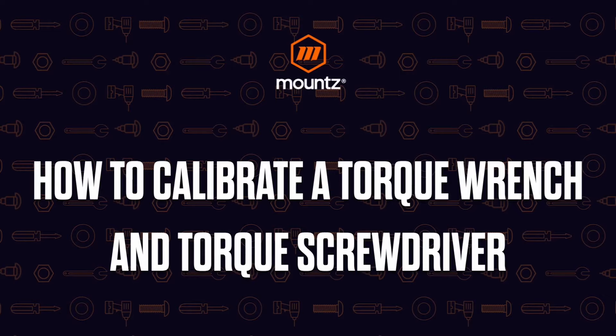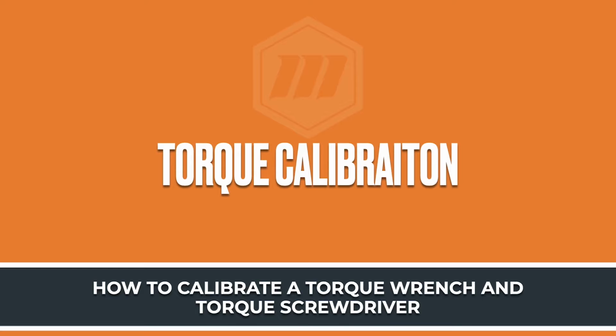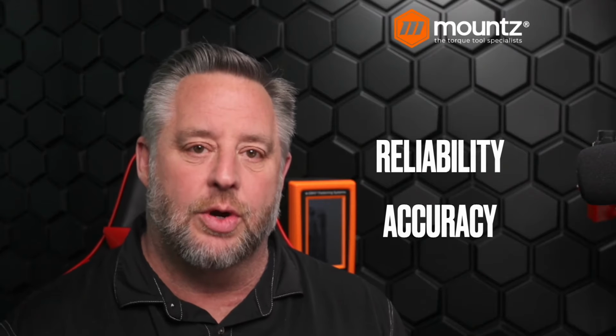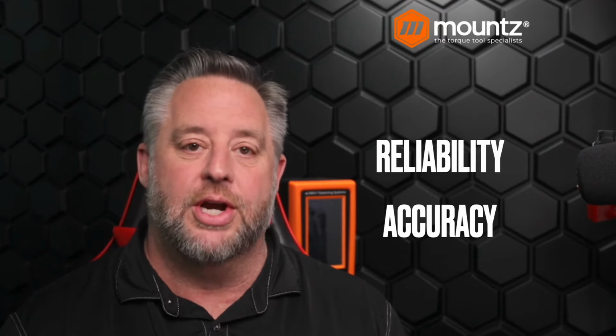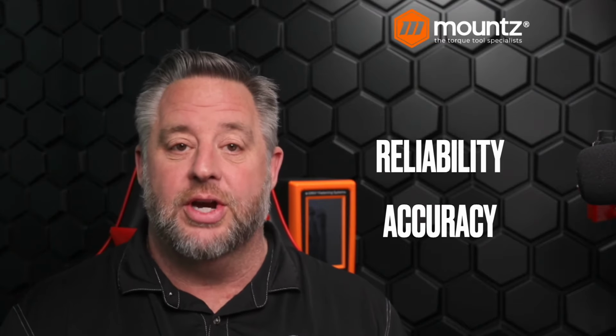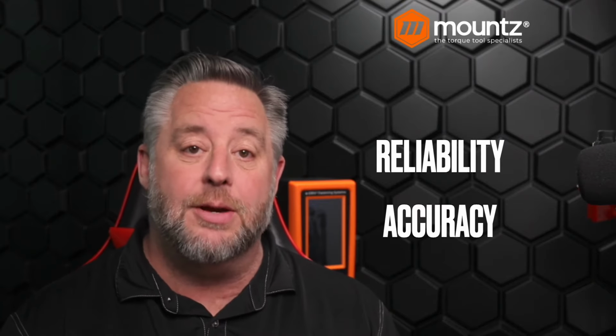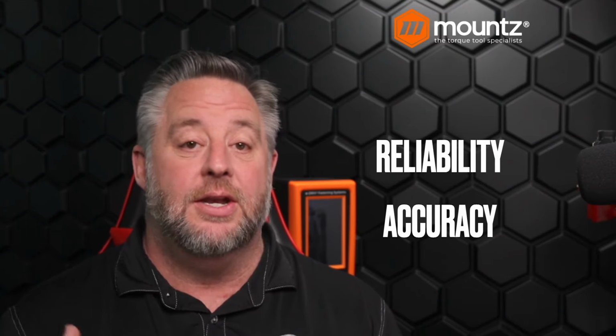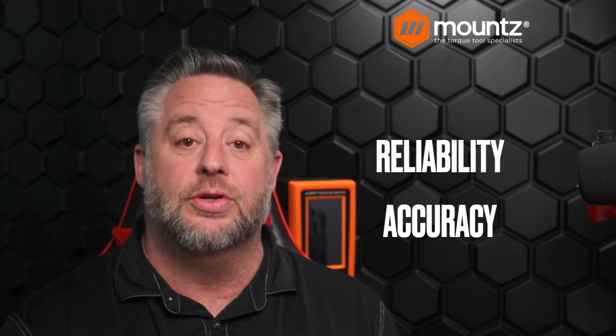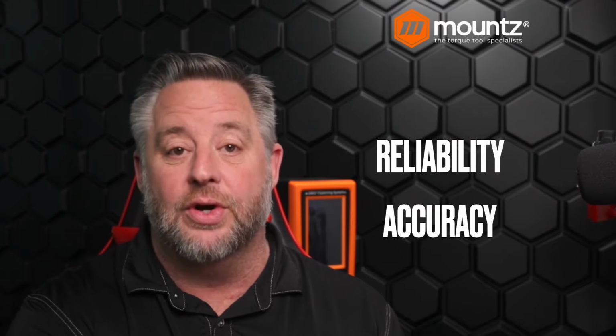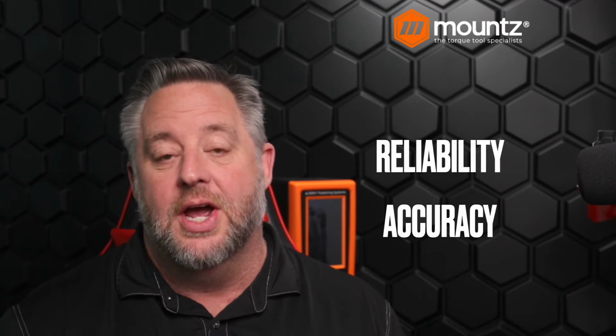But our topic for today is how to calibrate a torque wrench or a torque screwdriver. Now, the process of doing a torque calibration is not very difficult to understand or do, but there are some things that require a little bit of knowledge to know what's going on and how different things may affect the actual calibration process. The reason that we do torque calibration is to make sure that our tools are repeatable, that they're repeating accurately, so we can have some sense of reliability that these tools are performing regarding the torque output that we are looking to achieve, to make sure that we're getting the correct clamp force that we're trying to achieve with that fastener. So this is obviously the reason why we would do the calibration process.